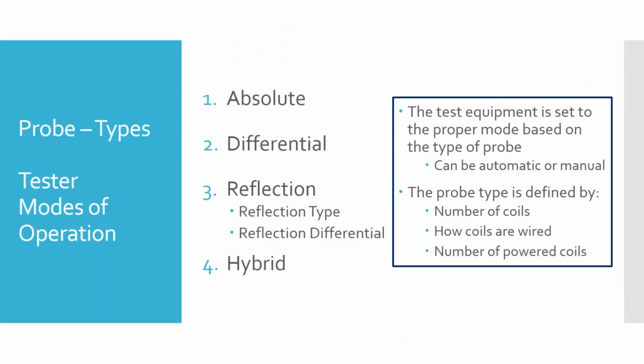So those are kind of the physical setups. Now we need to look at the probes themselves and the coils inside of them. They operate in different ways, they're run in different ways, and there are modes of operation where we have to match how the coils inside a probe behave to the signals we're looking for on our tester. They break down into, you can see I've got 4 things here, but really there are 3 types of coils, and the fourth one, the hybrid, is a combination deal.